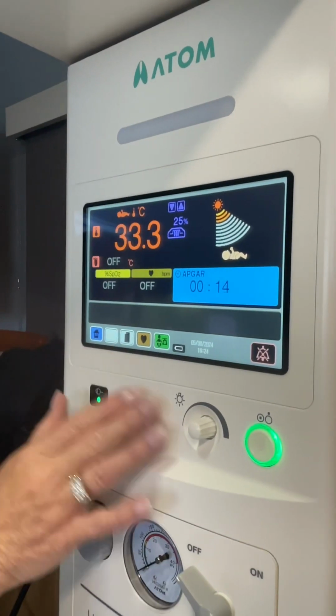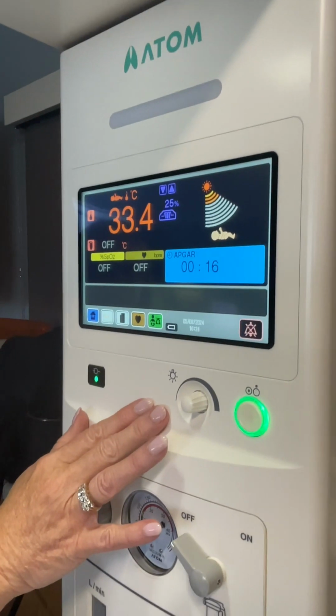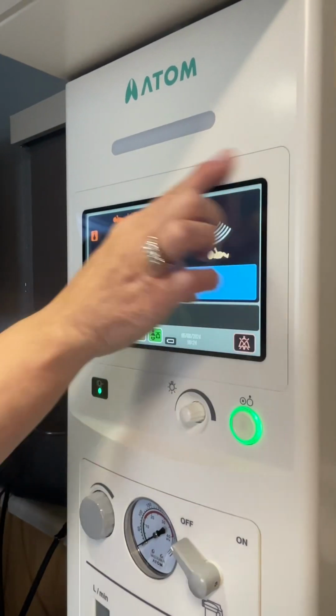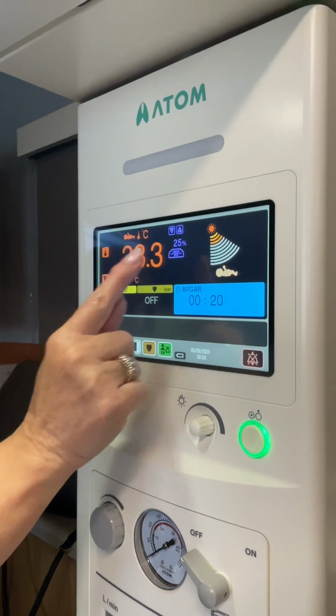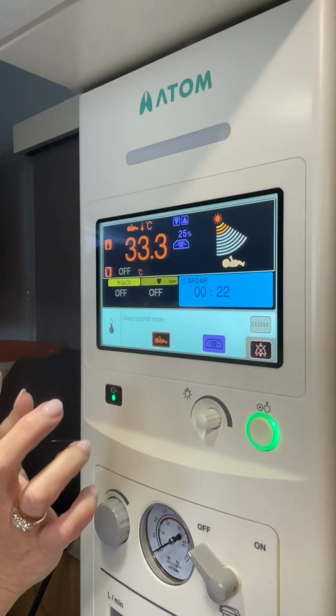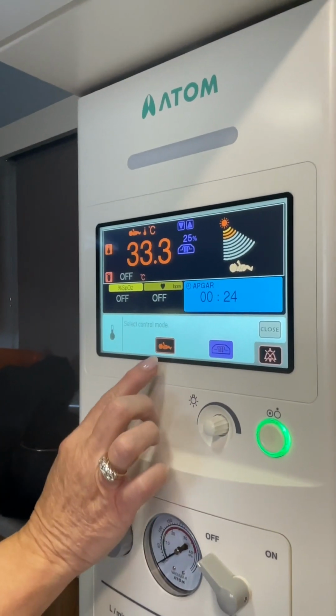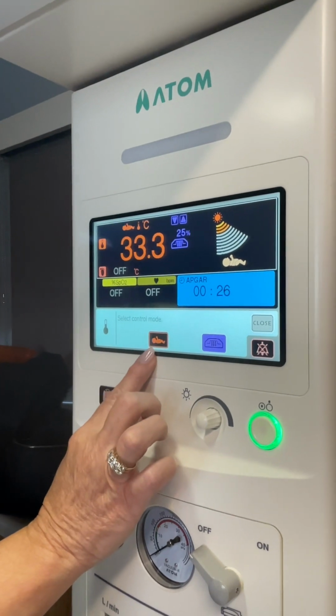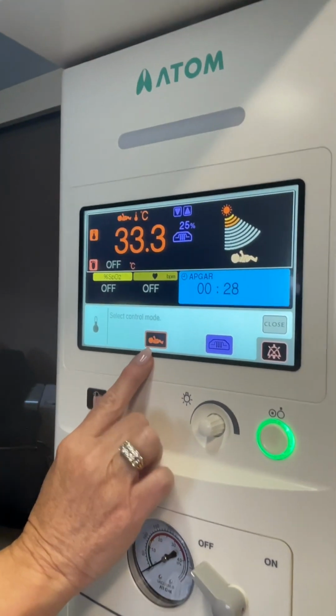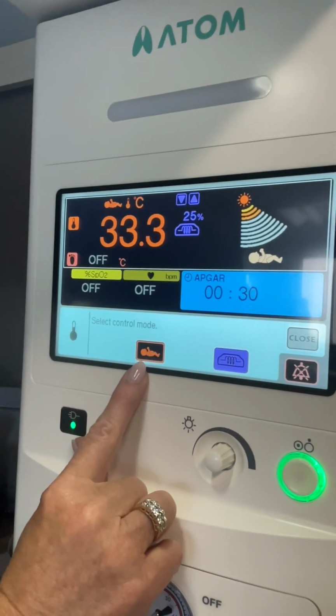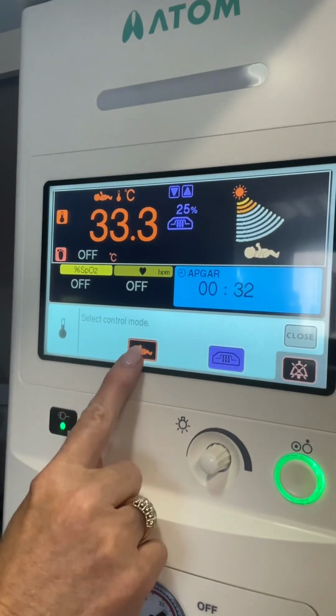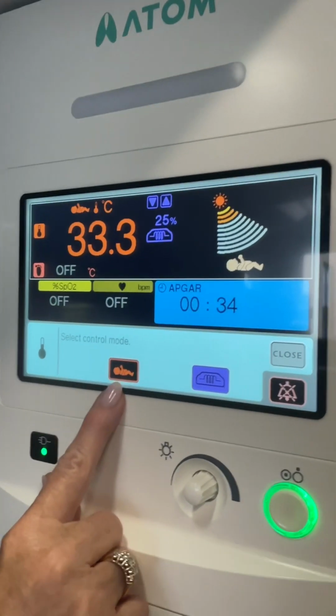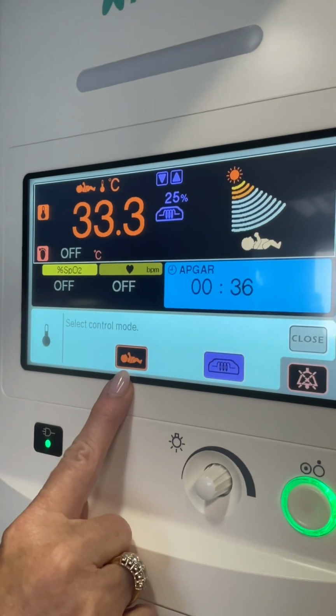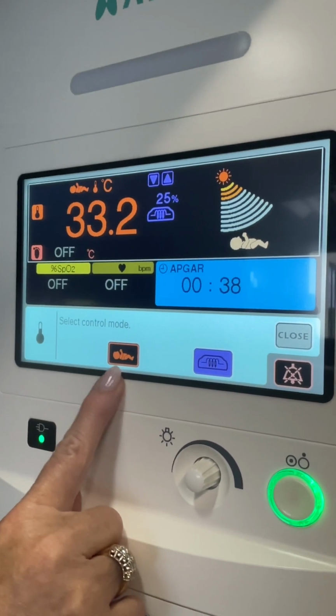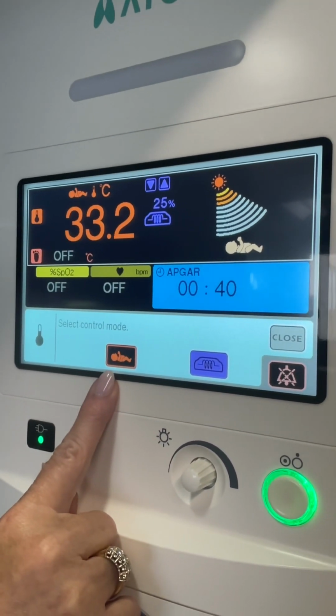This is our touch screen, but it's an intentional touch screen. So if you touch up in the upper half with not just a tap, but a little longer tap, it's not hard, just more time involved in your press. There's your servo mode or baby control, where the temp probe is on your baby's abdomen covered by a temperature probe cover, and that would mean that your baby is your thermostat. So as the baby needs heat, the heater turns on. When the baby warms up, the temperature will drop off.